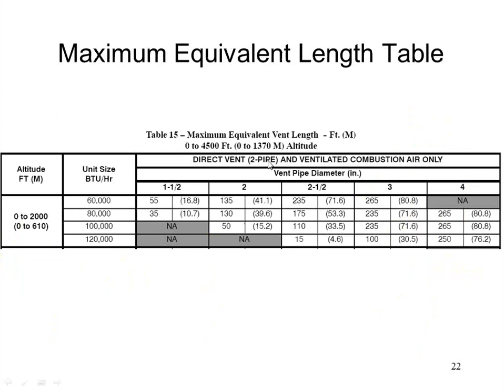These guys don't. I'm only showing you the first part of the vent table here. There's no reason to show you the higher altitudes because in the Midwest here, we are never above 2,000 feet, so the table gets really simple. If I want to look at some examples, let's say I take an 80,000 BTU furnace. If I want to run 2-inch venting pipe, I can go 130 feet with that one. So that's how far I can go.